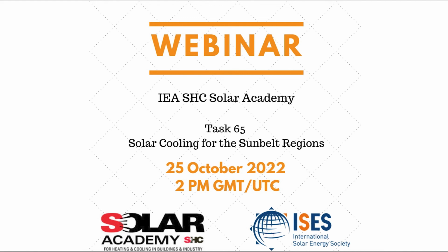What could be said is that the systems usually work for their nominal conditions. So be careful if you take a small-scale chiller developed for the European market, especially for markets like Germany and Austria, and you take that to Southern Europe - then it can already be worse from an energy efficiency point of view, as well as the capacity you get out of this machine. So you have to be careful, but that's the same, to be honest, for each vapor compressor chiller. If you take them from the normal conditions wherever they've been tested, and take them to a more interesting climate like in the Sunbelt regions, they will also not reach the high numbers you usually see on the paper of the product brochure. So that's something you should probably take into account for all kinds of technologies.